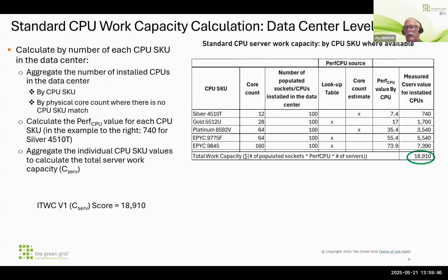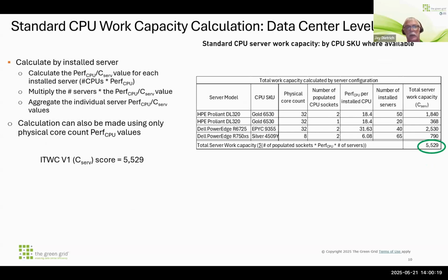So then you take those per CPU values and multiply them by the total number of CPUs in the data center to get your total CSERV value for each processor type. Then you accumulate that to get the total CSERV value for the data center. In this case, 18,910. That is your IT work capacity version 1, or CSERV score, for the servers in your data center.